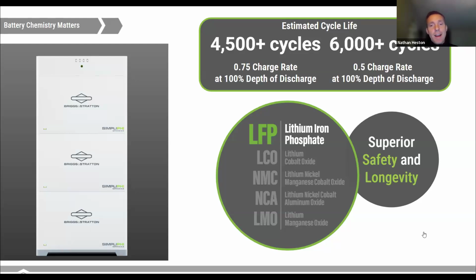It also has a very high power output. So one of the nice things about this battery is it can be cycled very fast. 0.75 charge rate is what you're seeing tested there. 100% depth of discharge, and you're still looking at over 4,500 cycles. 0.5 charge discharge rate, that would be a 2-hour charge, 2-hour discharge. 100% depth of cycle, you're over 6,000 cycles based on our lab testing.